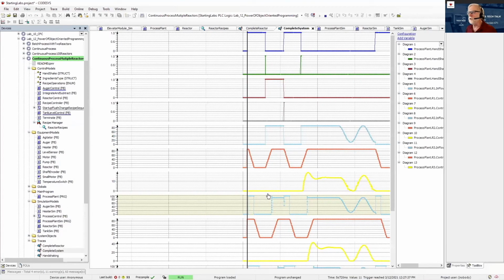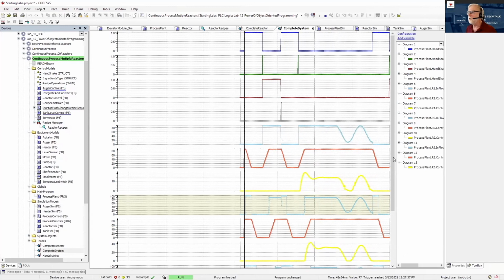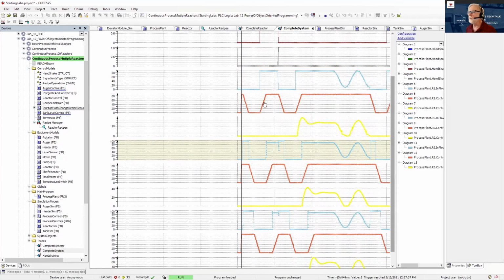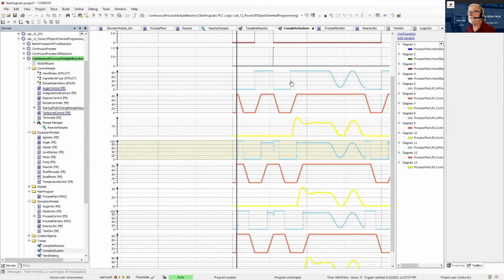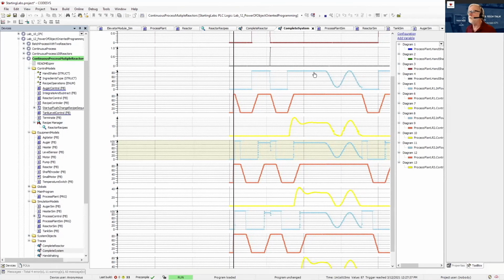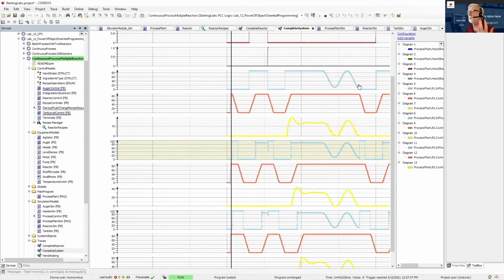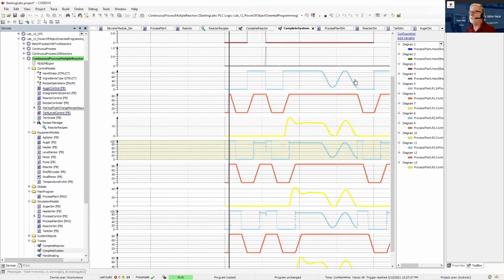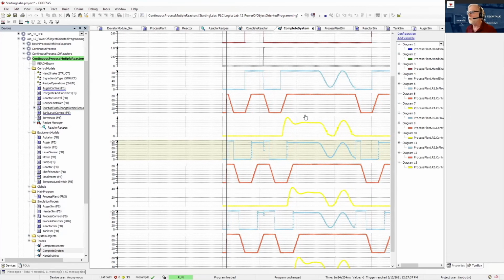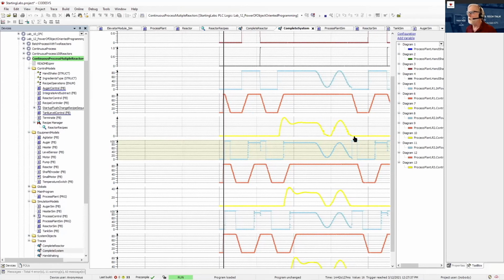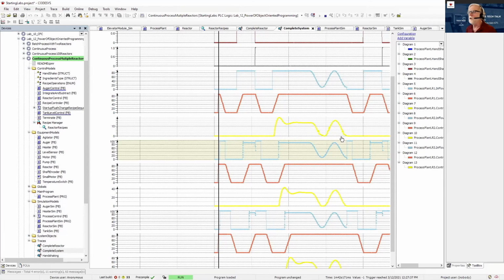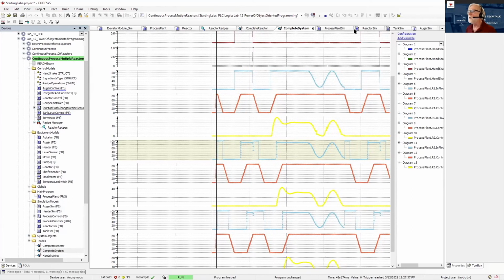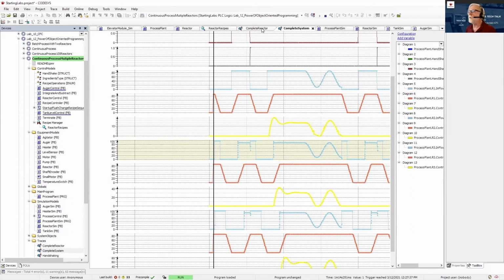Yeah, so we went through the flushing process. So here's the first tank, the second tank, and the third tank. And then this is the inlet flow rate. It goes into a constant speed flow for a while, and then it goes into this random flow just to make sure our control loops are all working properly. And yeah, they're working properly because now the variable speed drives are all varying their speed with respect to that motor.